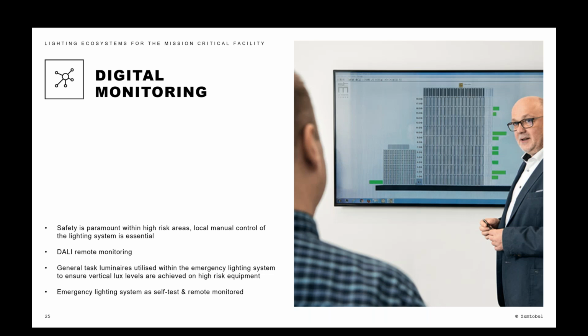Within these areas, when talking about safety, we tend to use the general task luminaires within our emergency scheme. We spoke earlier about dedicated emergency luminaires - this is slightly different, and the reason we do it is because within these plant areas, it's absolutely paramount that we get the right level of lux on the face of the plant and on the floor, so the people working on high risk equipment feel safe.